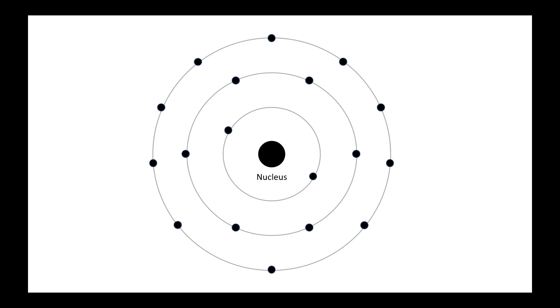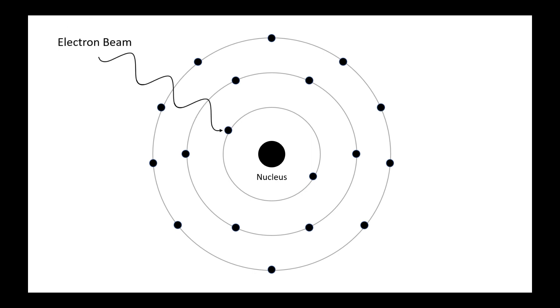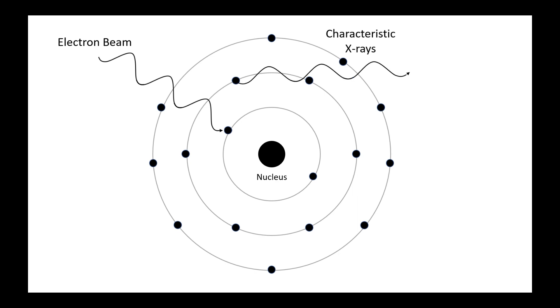When the high energy electron beam in the SEM interacts with the atoms of a sample, the beam electrons are able to knock out the inner shell electrons of those atoms. This forces the valence electrons to fall closer to the atomic nucleus and this process creates x-rays that are unique to each element. The EDS detector inside of the Phenom SEMs can detect and analyze these x-rays to determine a sample's elemental composition.